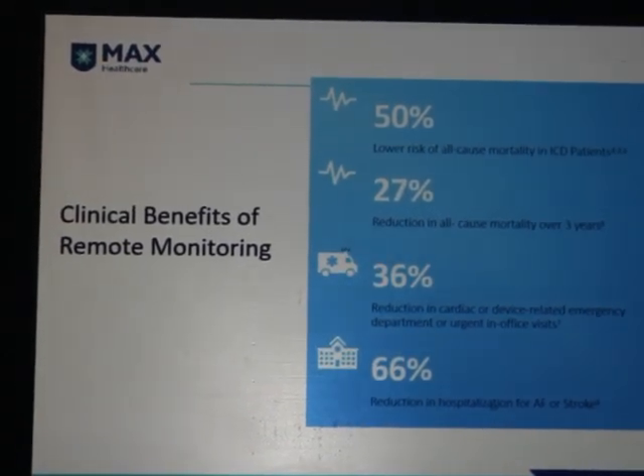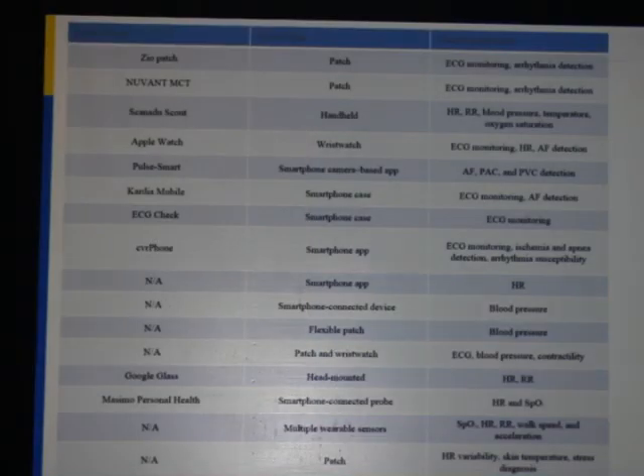So you can actually get a 6-lead ECG, because the 6-lead ECG is based on right arm, left arm, and the leg. Even when we record, for those of us in whose clinic ECGs are recorded, we know one electrode is put on the right arm, one on the left arm, one on the leg, and that gives you the frontal plane ECGs: 1, 2, 3, aVR, aVL, aVF. aVR, aVL, aVF are derived from it actually. And then you have the chest leads, which are separate, so that gives you 12 leads. So you don't get the complete 12 lead, but you can get a 6-lead ECG out of the AliveCor device, Kardia. So that is also something which can be done and might be available from time to time.